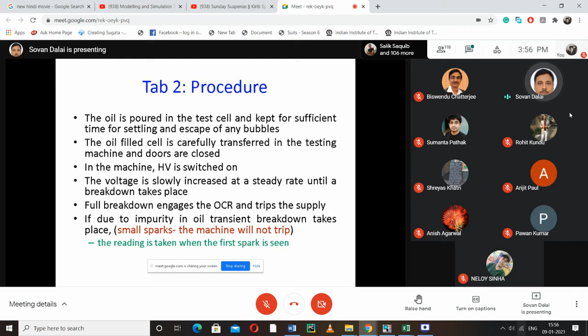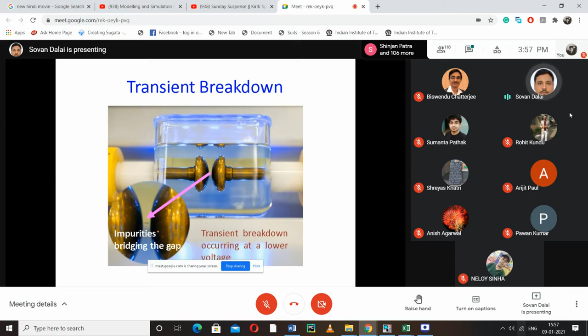This is the broader view of the test cell. This is the mushroom type of electrode, and here we have to maintain the tip to tip gap distance of 2.5 millimeter. This is the brass electrode, and the spark is shown like this. When I show you the video, you observe this spark also. A transient breakdown is of lower intensity, because some of the impurities are attached to the electrode, so the gap distance is reduced. Due to that, a transient breakdown may occur in a particular oil sample test.